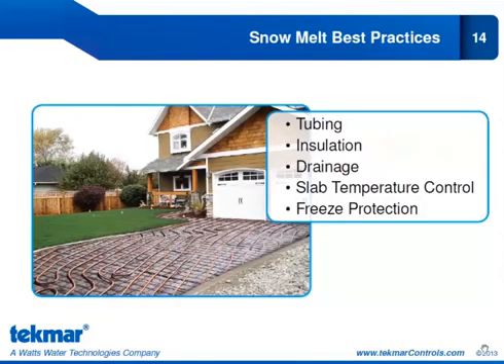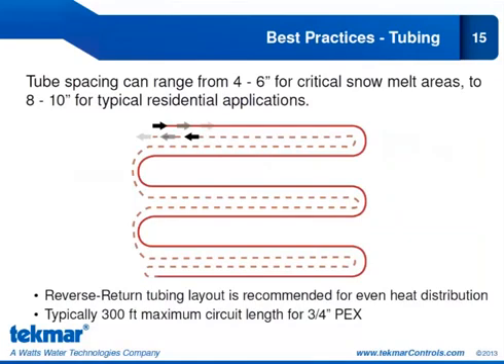We'll now look at best practices for snow melting, covering tubing, insulation, drainage, slab temperature control, and freeze protection. For tubing, spacing can range from 4 to 6 inches for critical snow melt areas, to 8 to 10 inches for typical residential applications. A reverse-return layout is recommended for even heat distribution. The typical maximum circuit length for 3/4-inch PEX is 300 feet — it is not advised to exceed 300 feet.